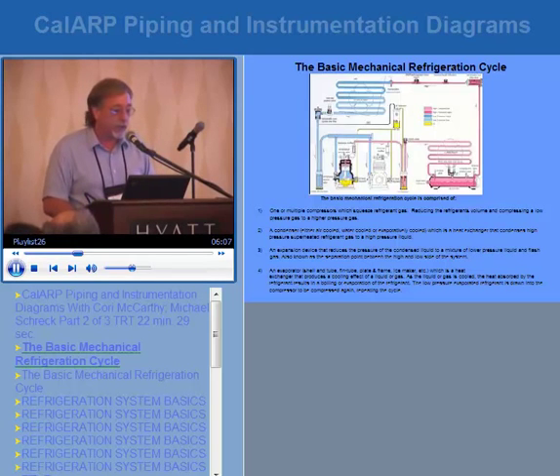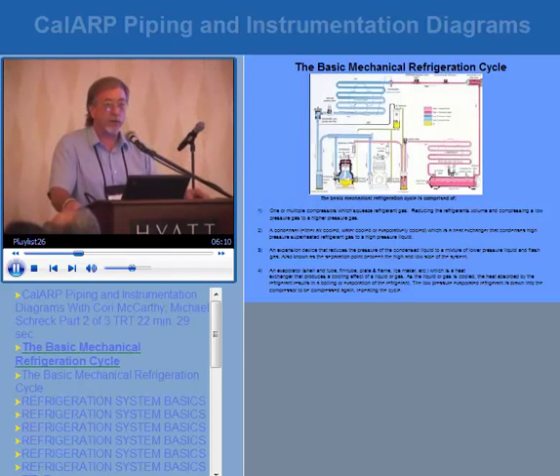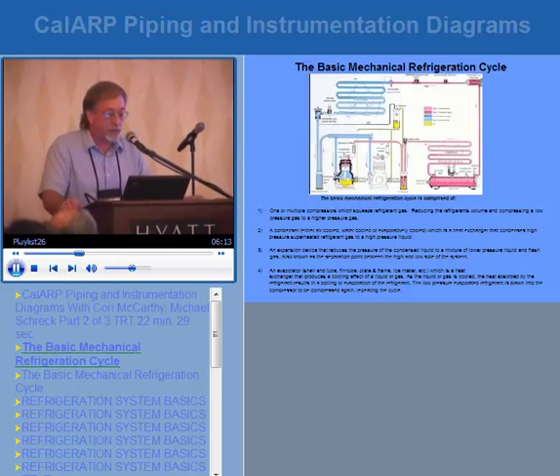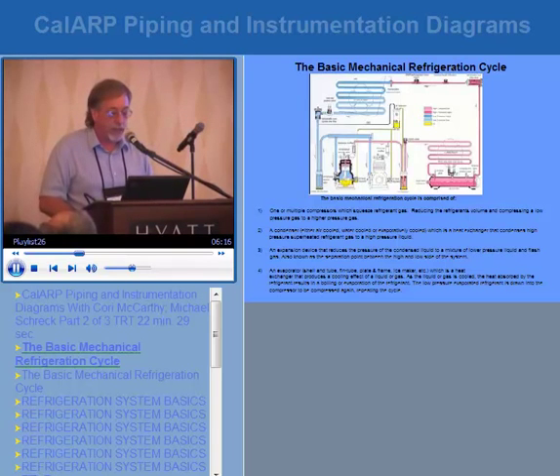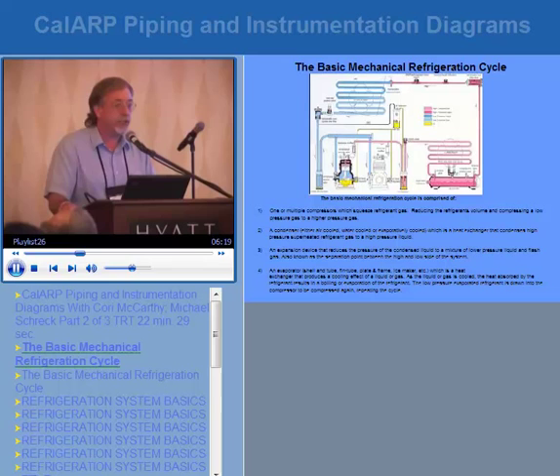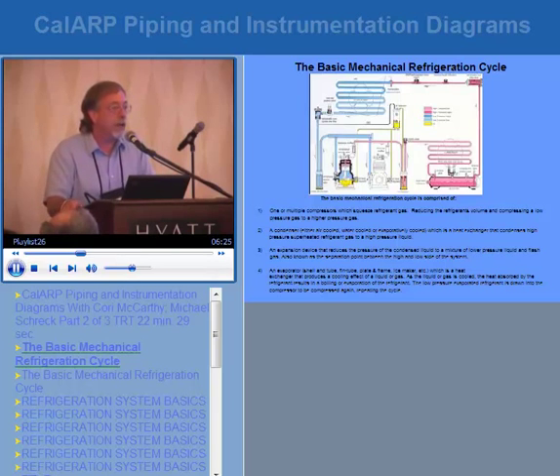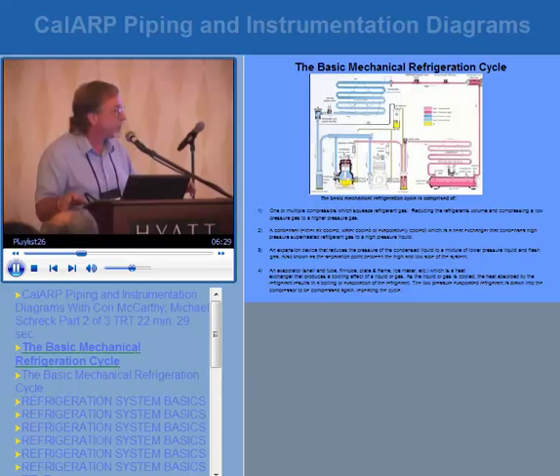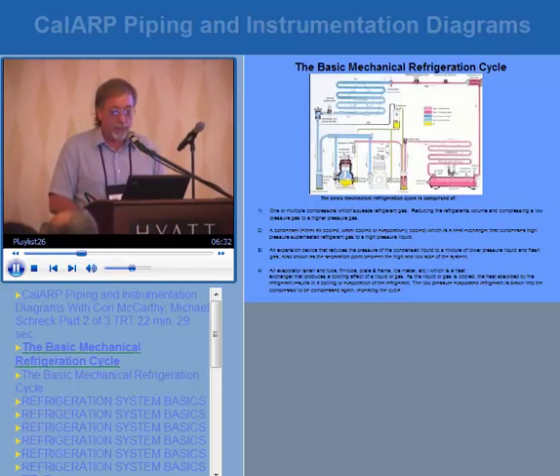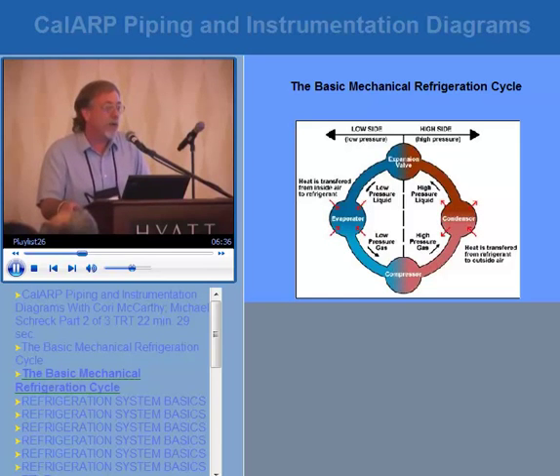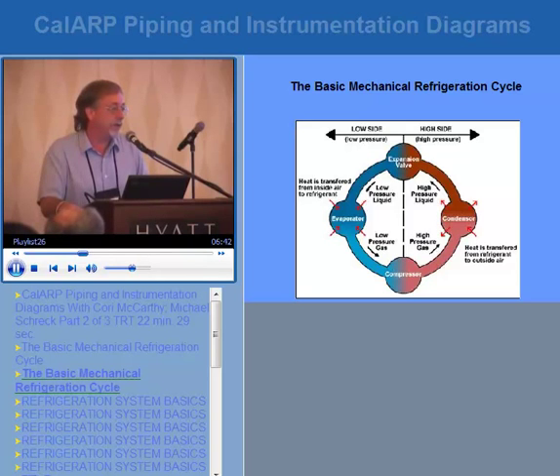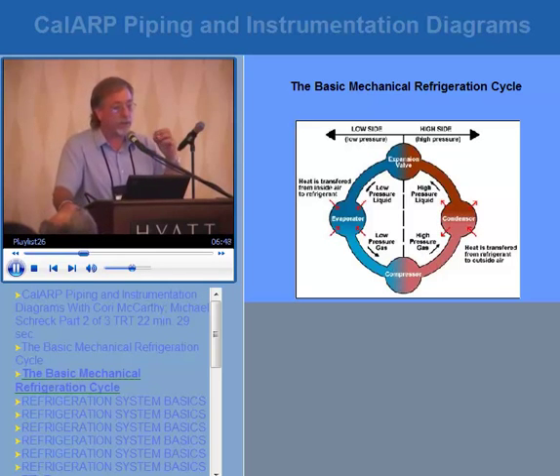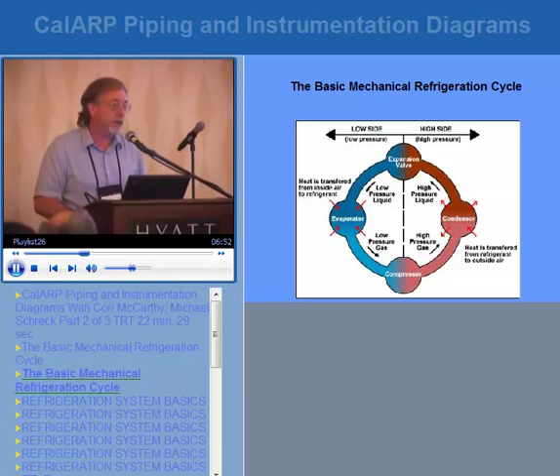In addition to vessels, you'll run into evaporators hanging from ceilings — those are air units where we absorb the heat into the system — and other things like chillers and shell-and-tube heat exchangers. Outside, you will see the condenser where we reject the heat from the system, and the other major component is the compressor. A lot of P&IDs don't show you what the equipment looks like. The best thing you can do on a P&ID is color-code it so you can follow the lines and know whether it's the high side or low side of the system.